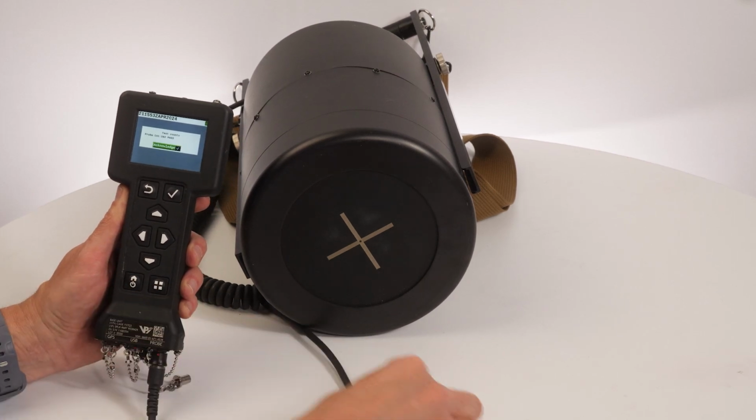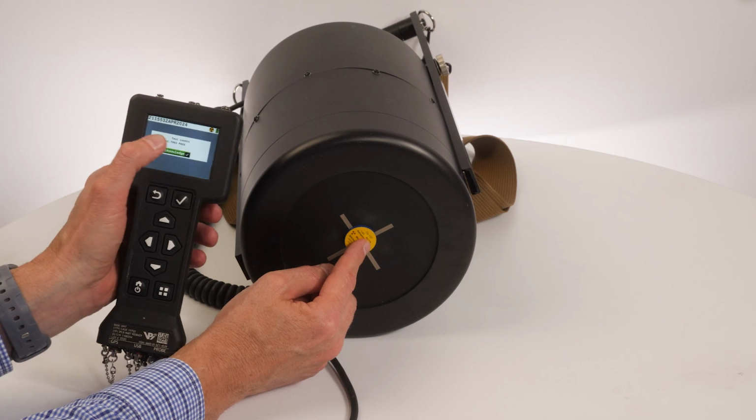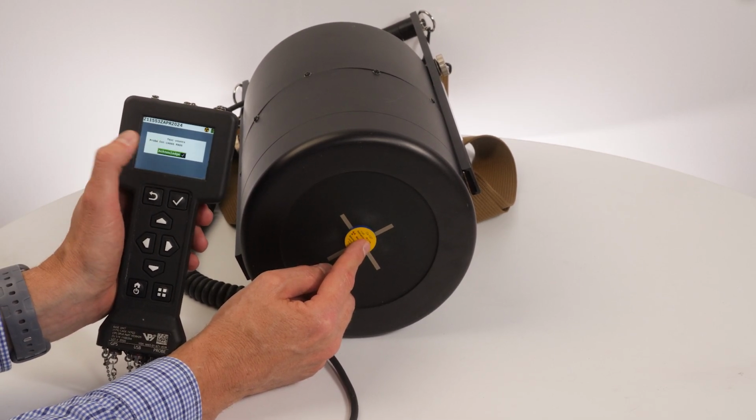Leave the FIDLER Probe in direct contact with the check source for 1 minute. Verify that the probe CNT or count displays at least 1 count or higher and displays pass. After the 1 minute, press the Enter key to acknowledge the rad test results.